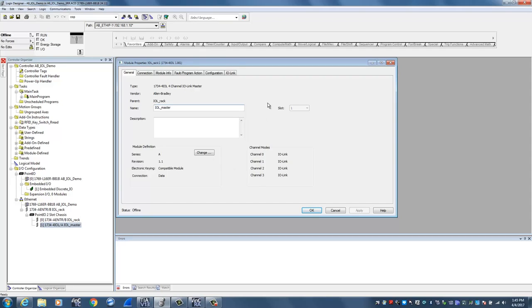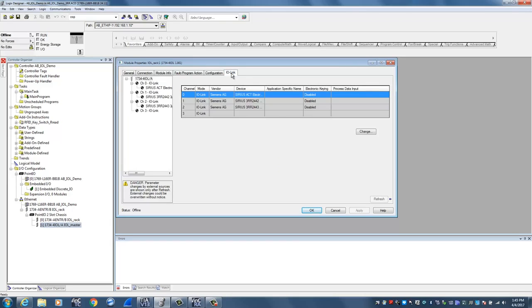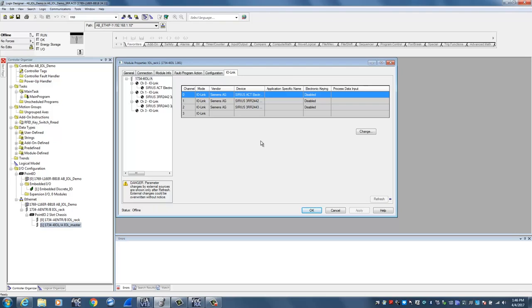Once you have them set up as IO-Link devices, to add the individual devices come over here and click on the right-hand tab labeled IO-Link. You can see in this project we've configured the first three out of the four channels as IO-Link devices. The first one being an electronic RFID key switch that Siemens offers for access control on a machine, and the second and third devices are a pair of three-phase current monitoring relays that are used to measure current, voltage, and power off of a system.